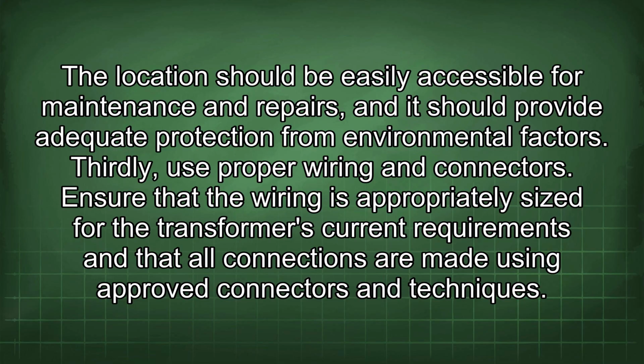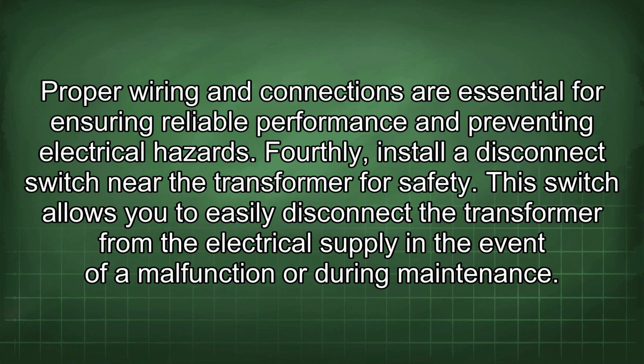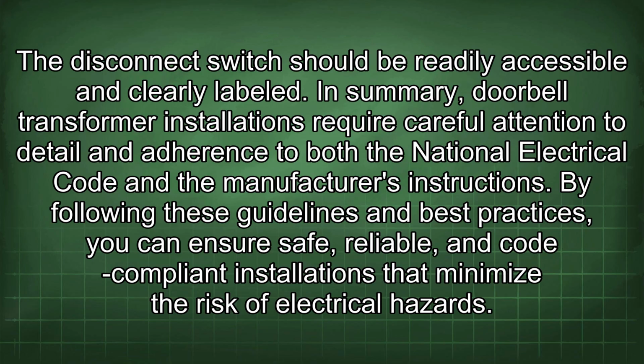Thirdly, use proper wiring and connectors. Ensure that the wiring is appropriately sized for the transformer's current requirements and that all connections are made using approved connectors and techniques. Proper wiring and connections are essential for ensuring reliable performance and preventing electrical hazards. Fourthly, install a disconnect switch near the transformer for safety. This switch allows you to easily disconnect the transformer from the electrical supply in the event of a malfunction or during maintenance. The disconnect switch should be readily accessible and clearly labeled.